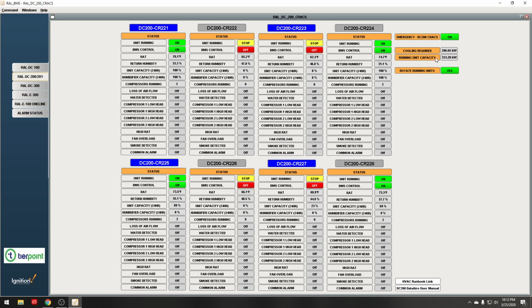So that's slick, really protecting us from putting too much load in the space. If units fail and we don't have time to react, there's a little bit of automation that detects it can't cover the room, there's too much heat load, and it kicks everything on to get a sufficient amount of cooling. Then we can manually investigate and manually turn off units as we need.